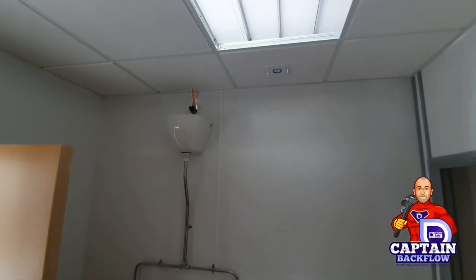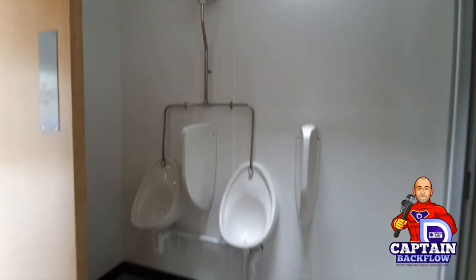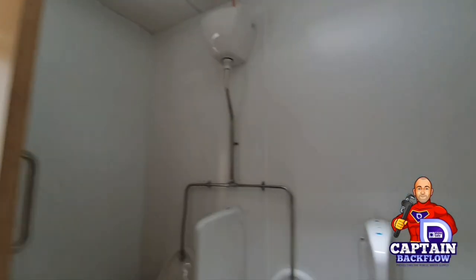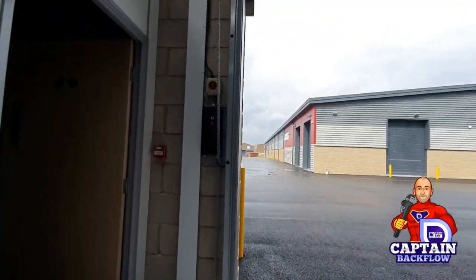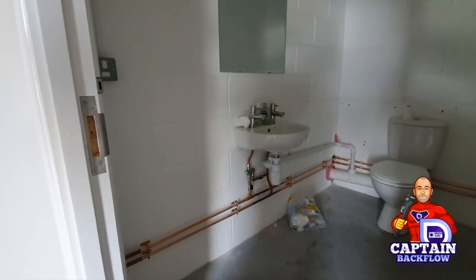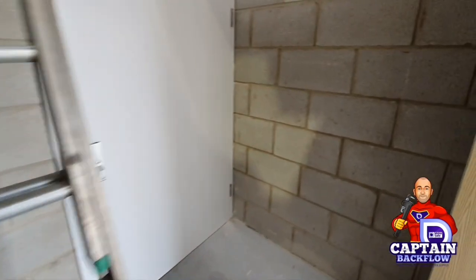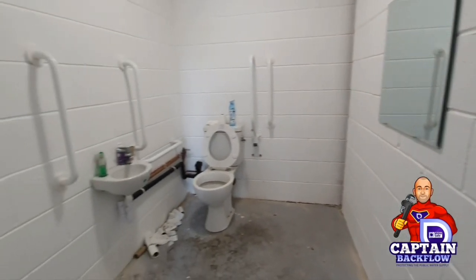There's a TMV on it from Delabie. What we're looking at here is the AUK2 air gap on the urinal system, which is a requirement. Also up at ceiling height there is a Thomas Dudley urinal control device. Going into the warehouse you can see staff are turning up — the facilities are starting to be used. That is the basin I hung with the chemical fixings. It's got a TMV, single checks on it, and the toilet — you can see there's a bit of expanding foam there and the decorators still have to make good. And that is what was the existing accessible toilet.